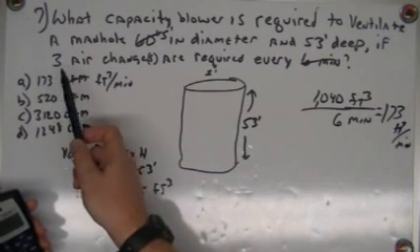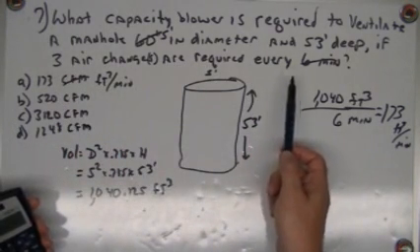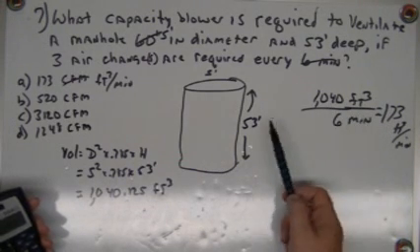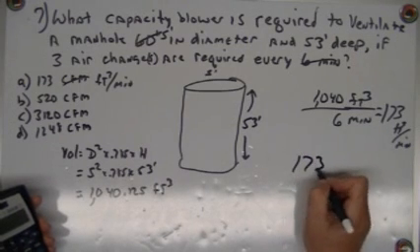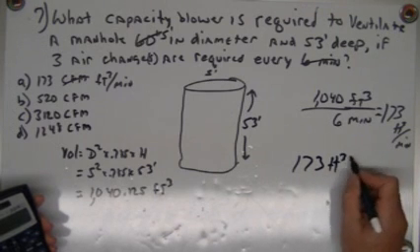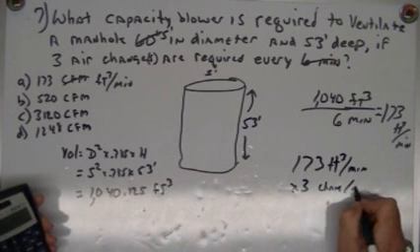And there's something over here that says 3 air changes are required every 6 minutes. So in order for this to do 3 times every 6 minutes, the fan is going to have to be 3 times bigger. So I'm going to take 173 feet cubed per minute times 3 changes per minute.